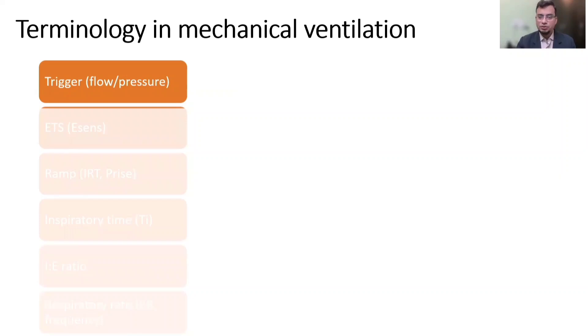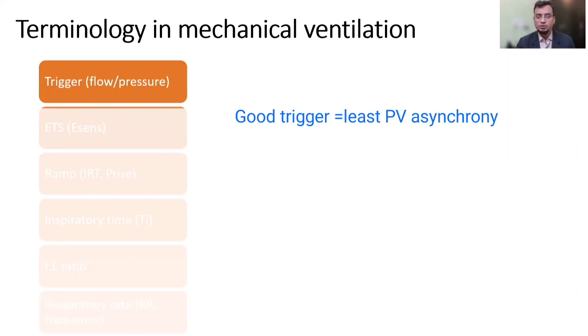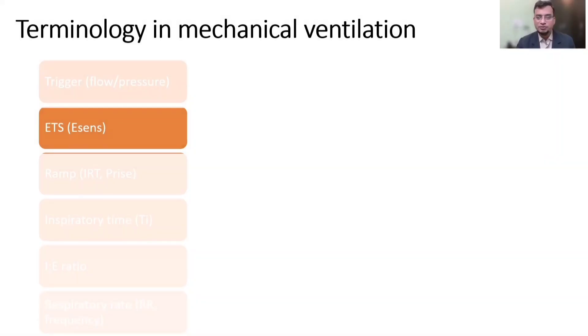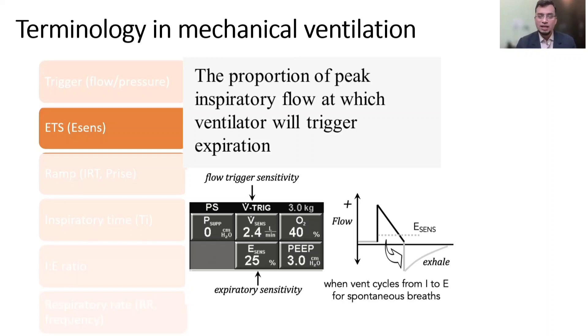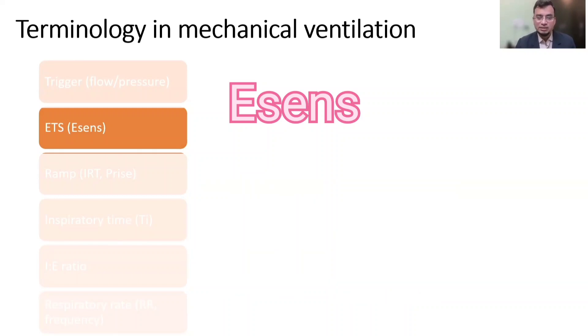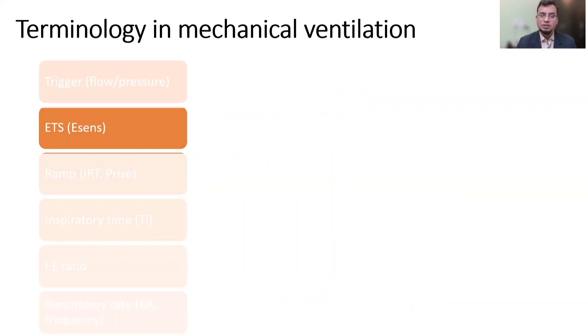Trigger refers to the signal that causes inspiration. When the patient is set on assist control mode or spontaneous mode, a trigger setting is required. An optimal trigger reduces patient-ventilator dyssynchrony and reduces patient discomfort of breathing. Triggers can be of two types mainly: flow trigger and pressure trigger. Neural and shape signaling are the latest types of trigger mechanism. ETS stands for expiratory trigger sensitivity — it is the proportion of peak inspiratory flow at which the ventilator will start cycling. By default, ETS is set at 25% of peak inspiratory flow.